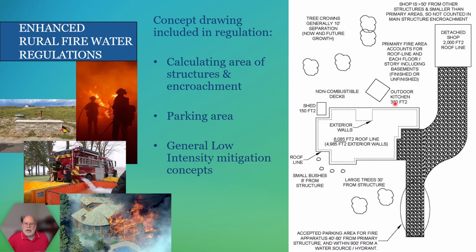hazards. Now, if we have something outside the 50-foot encroachment, as an example here, where we have a detached shop or garage, but it's 50 feet or more from the structure, then that area does not have to get calculated in. Unless this shop, for example, becomes a larger square footage than your primary structure, now that square footage is what's going to drive the water supply.